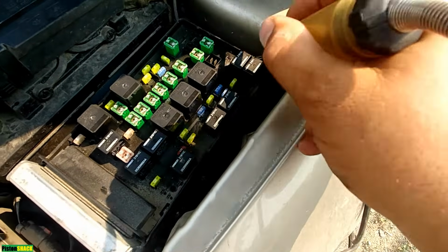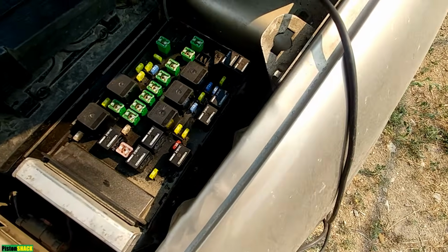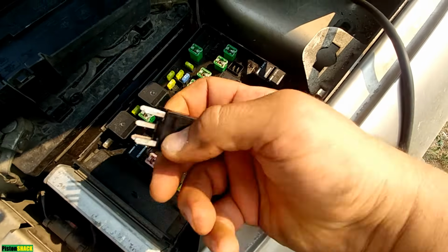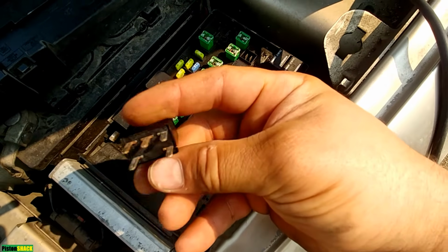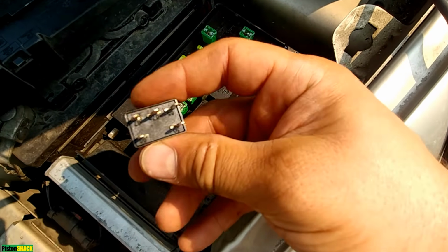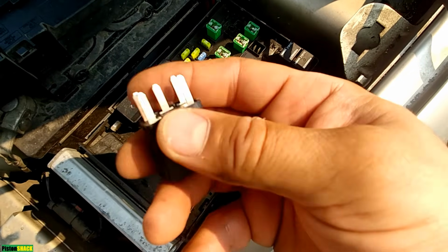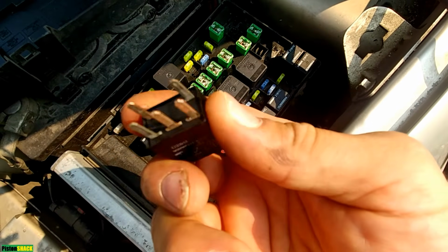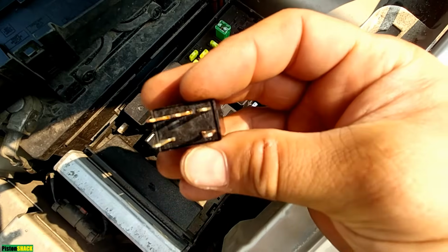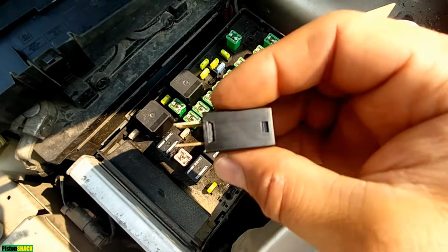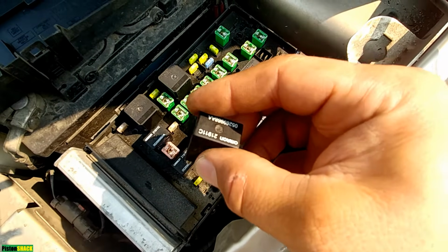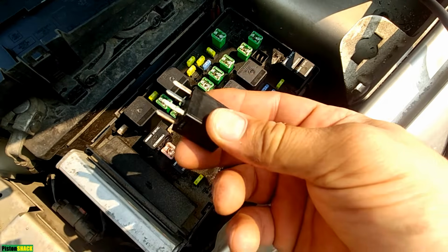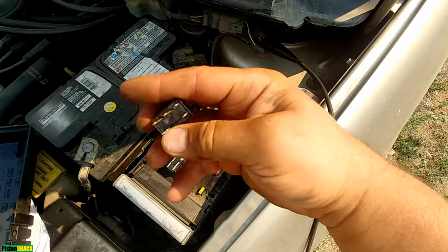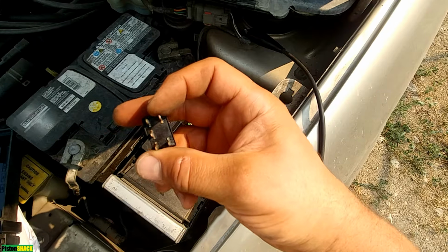For example, if you swap it and nothing happens, you need to pull it out and check for rust, corrosion, any moisture intrusion, or burned terminals. As you can see, there's no sign of that. The relay is good, visually it looks okay, and I know this relay is in good condition and not the problem.